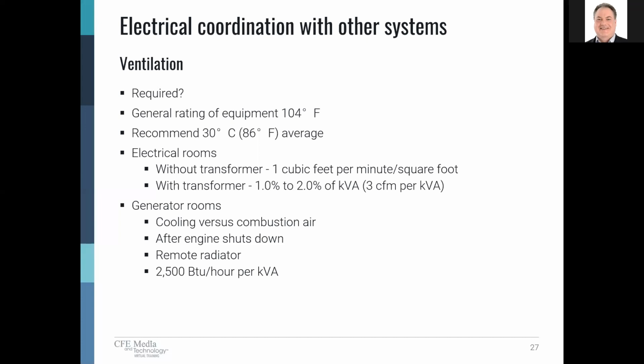Generator rooms are, again, a whole other topic, but you need to understand the difference between cooling and combustion air. The air going into a generator room is of 2 types: that for cooling, which you normally associate with the radiators, and the amount of air that's used just for combustion of the fuel. Radiators are normally located in the room, but they can be located outside the room. Once you locate them outside the room, you significantly reduce the amount of air, because combustion air is a small fraction of the total air needed by a generator.